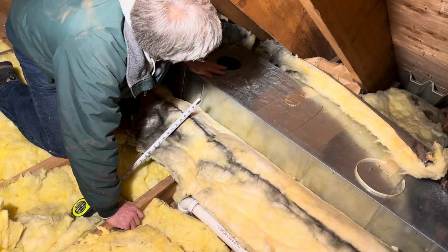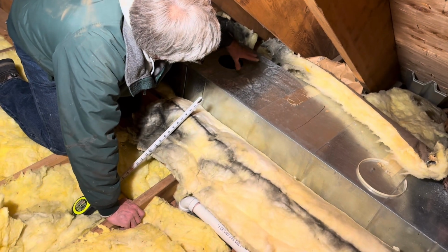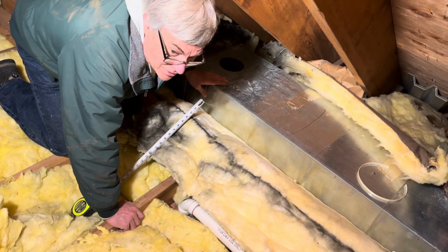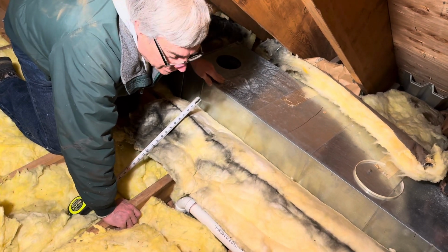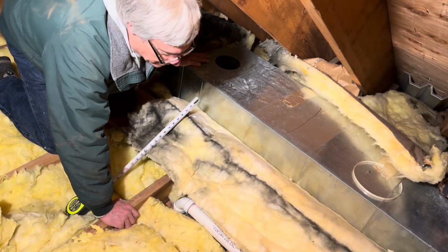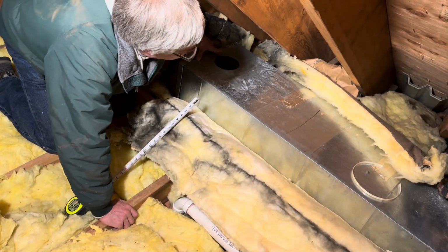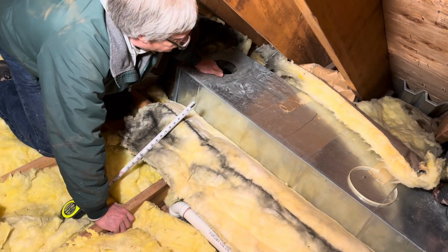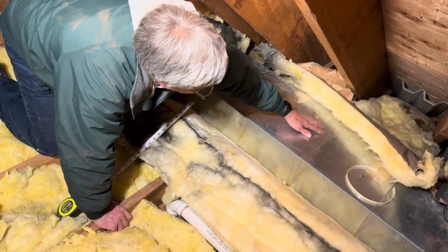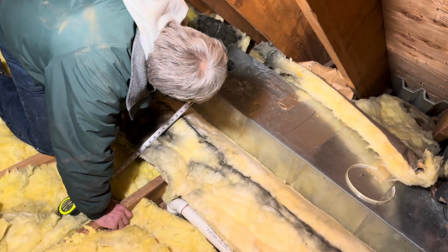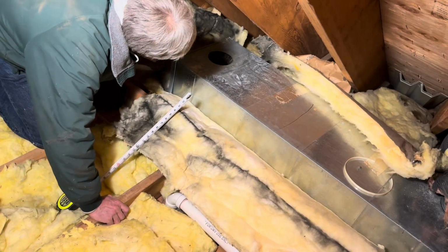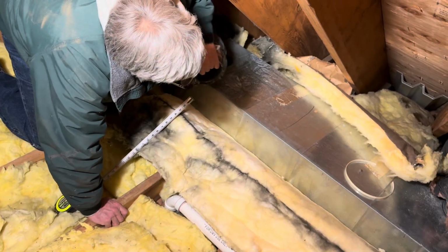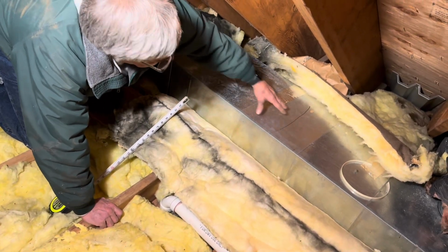So we're going to seal this. We're going to put some mastic on it, and then a piece of metal, and then we're going to put screws in it, and then we're going to put a mastic tape that will not, over time, dissolve into something like sugar and crisp up. We're going to use a quality product to maintain the longevity of the system. So this needs to be sealed and put somewhere up here so that we can adequately supply. And we're going to have to make this longer, obviously, so we can adequately supply the area that it's supposed to condition.